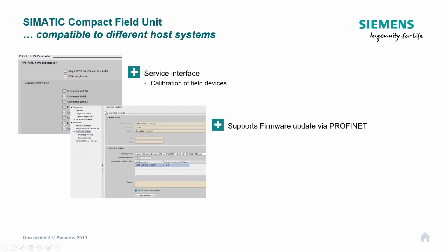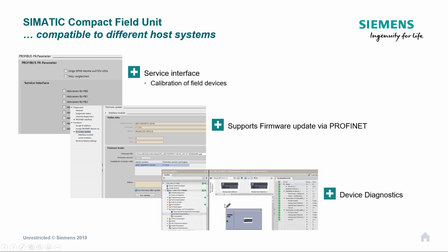Okay, another nice thing with TIA portal, because it sits on Profinet, you can upgrade the firmware of the Compact Field Unit. Now I do need to do that on mine, so when I do it, I'll record a video so you can all see how it's done. And the device diagnostics, again, they come through on PCS7, but sorry, I haven't got a screen for that. This is TIA portal. You can change the name of the device here, and that's what you'll get displayed on the front of your S7 1500 PLC. We're showing it on TIA portal, but because it's got a GSD-ML, really any PLC that supports Profinet will be able to have one of these devices on.